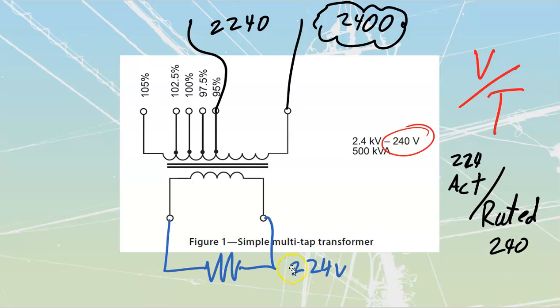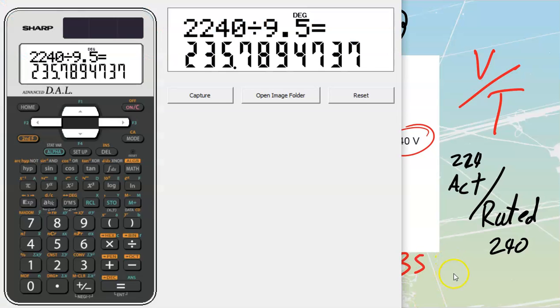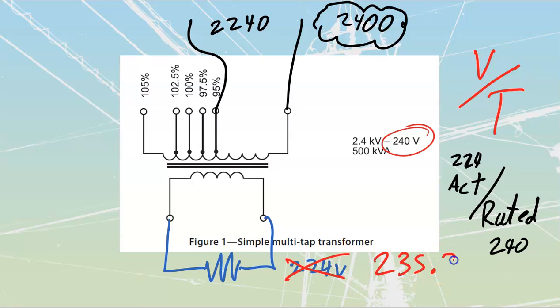It tells me that now what we would have adjusted this to is, instead of us operating at that super low voltage, we are now going to be at 235.7, so almost 236 volts. Pretty close to our desired value of 240. This is the way that we calculate it in the field.